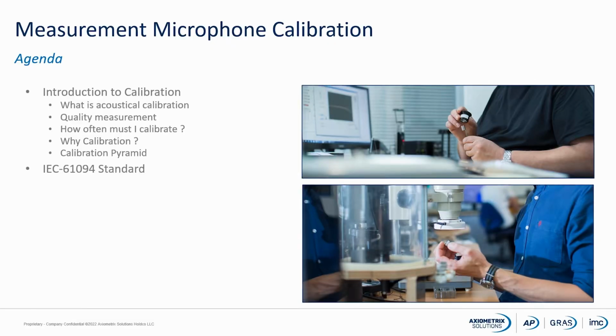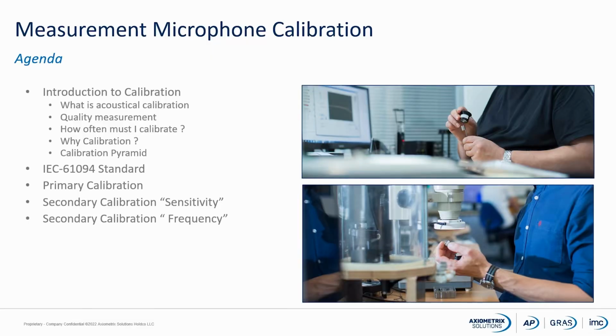When we are talking about measurement microphones, when we are talking about calibrations, then we also have to have a look at the standard for measurement microphones, the IEC 61094, because this standard describes how to calibrate, how to do a primary calibration, the high-end calibration of reference instruments. It also describes how to do secondary calibration. Secondary calibration is the calibration of the daily used instrumentation. In this webinar we will discuss secondary calibration of the sensitivity of the measurement microphone. We will also discuss the calibration of the frequency response of a measurement microphone.